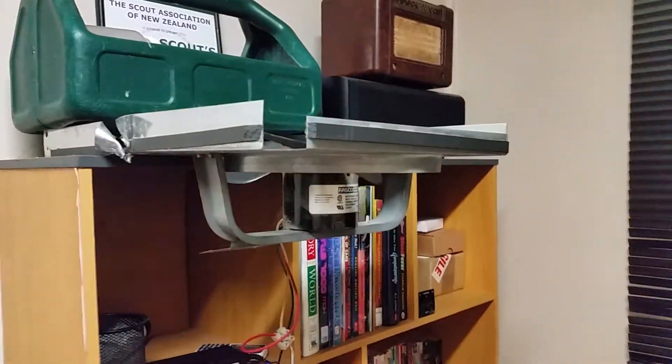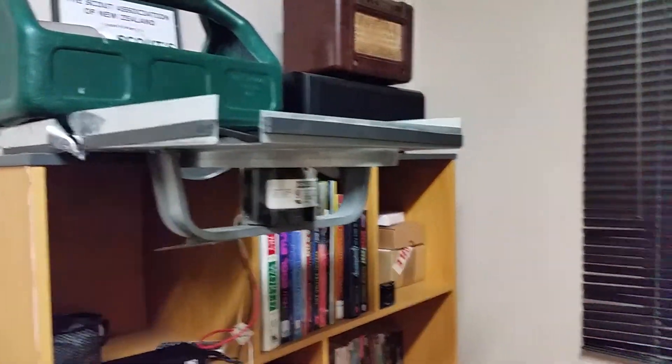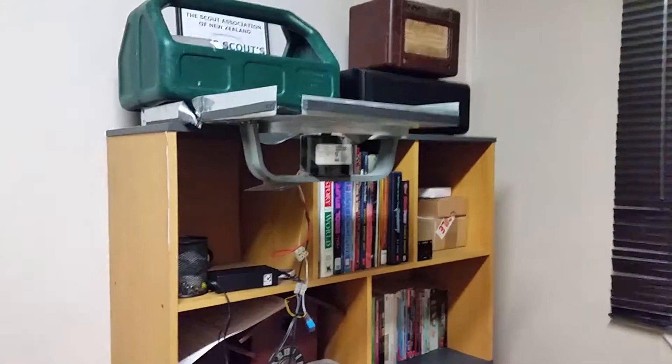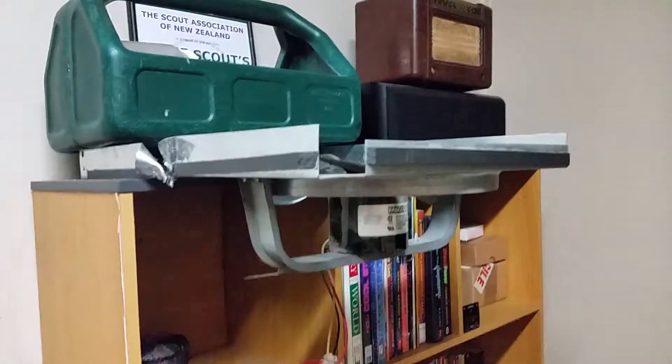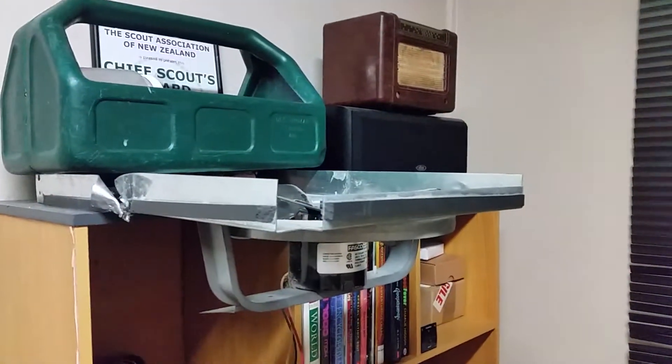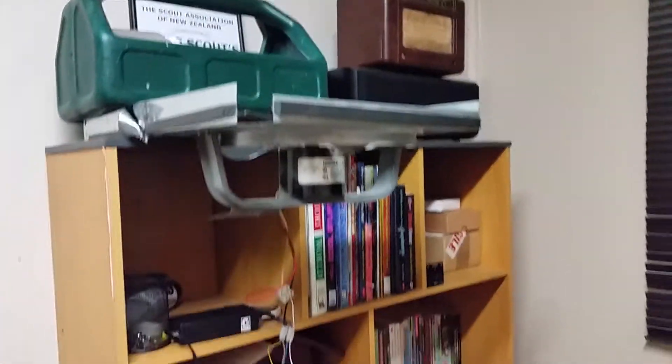There are multiple purposes for relays in a fire alarm system: doors can automatically close, extraction fans can turn on to evacuate smoke from buildings, HVAC units as in this case will turn off, and there are dampers that can automatically close to stop smoke exiting the building or going into separate rooms.